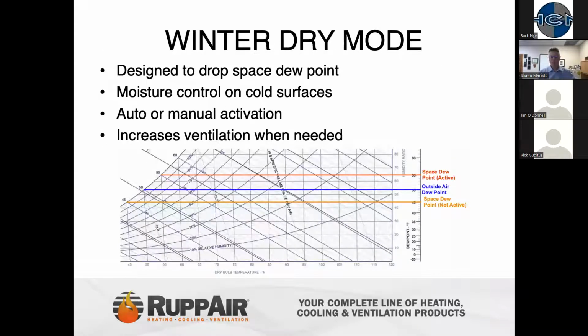So within the controls, also having some nice capabilities to control things beyond just the winter heating, but also we've incorporated what's called a winter dry mode. What a winter dry mode can be utilized is most commonly in these spec style buildings. We have a lot of post-construction moisture that may exist from everything drying. Having the ability to look at dew points within a space to dew points of outside, and knowing when it's logical to bring in more outside air for ventilating the system.